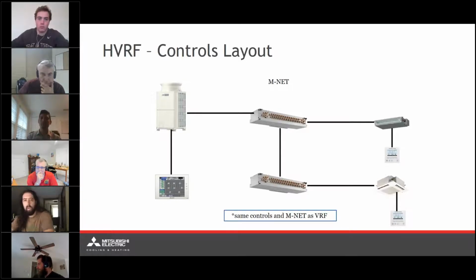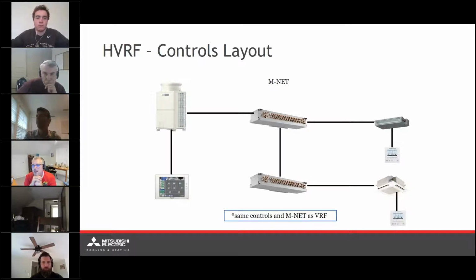Just want to use a slide to demonstrate that the controls layout for the HVRF system is the exact same controls layout as it would be for a standard City Multi VRF system. Everything is single point controlled, single point transmission wire from unit to unit, daisy chained. So ultimately, it's going to be the same M-NET, or Mitsubishi network, for the VRF system.